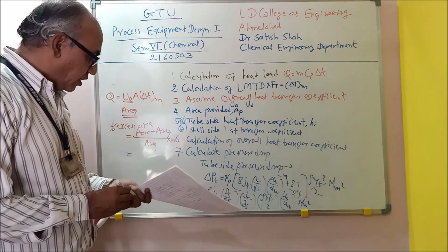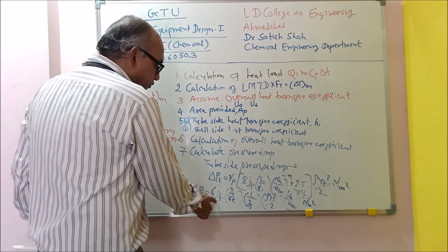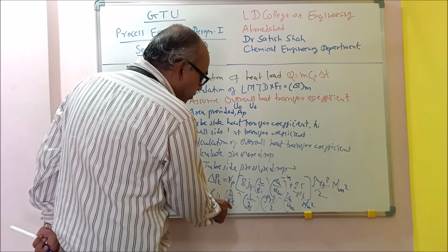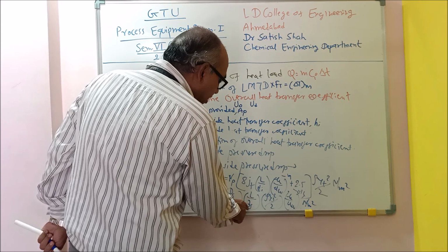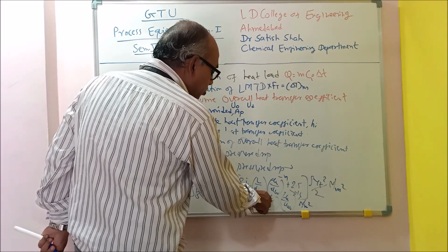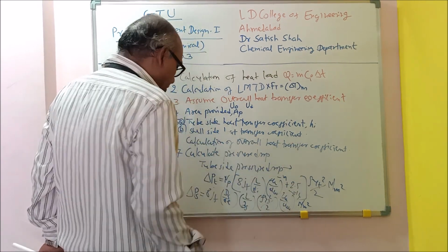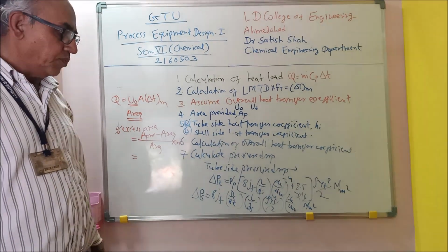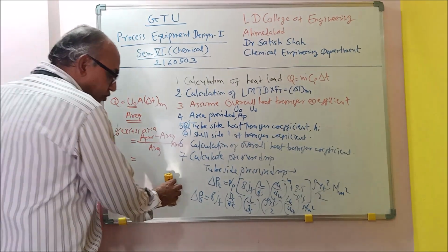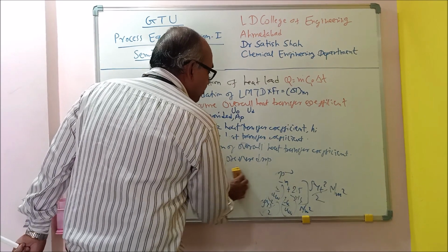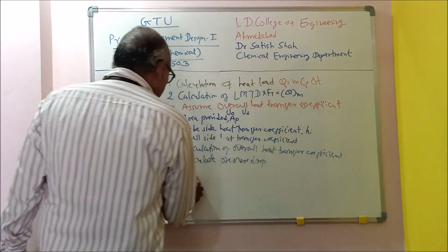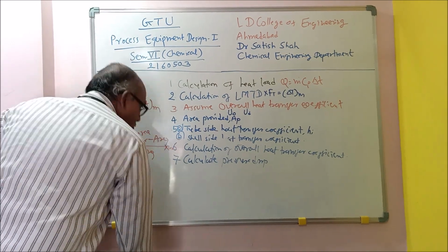Here also, JF is the factor which is given in the book chart, ds is shell ID, DE equivalent diameter, L and BS are the tube length and baffle spacing, rho density, US velocity on the shell side, and that will give you the shell side pressure drop. So this way you will calculate the pressure drop value. If the pressure drop on both sides is less than the allowable pressure drop, then we can say that our design is okay.